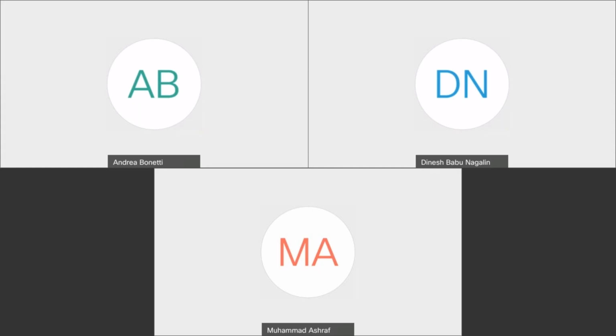But that GOOSE message with value 1 will be sent also if the protection function is blocked by the application with the physical blocking signal. You send a trip signal when the protection function is blocked. This is not wrong. It is wrong for me because I want to test the application and the settings of the relay, but for you, testing the GOOSE messages, it's not wrong. You don't care about that. So the digital twin fills the gap. Only Siemens can create a digital twin for the Siemens relay. Nobody else. Only Megger can create the digital twin for the Megger test sets. And only Omicron, since you are talking about Omicron, can create a digital twin for the Omicron test set.